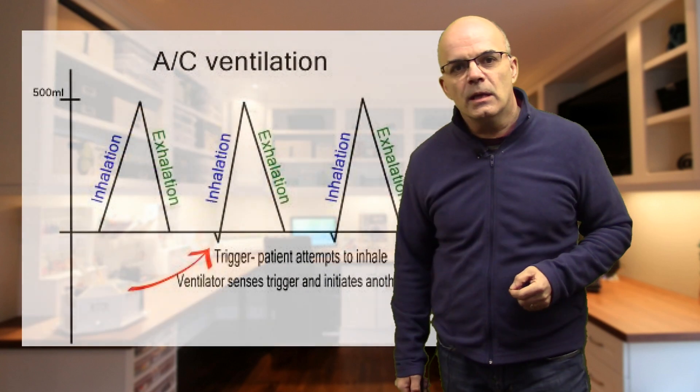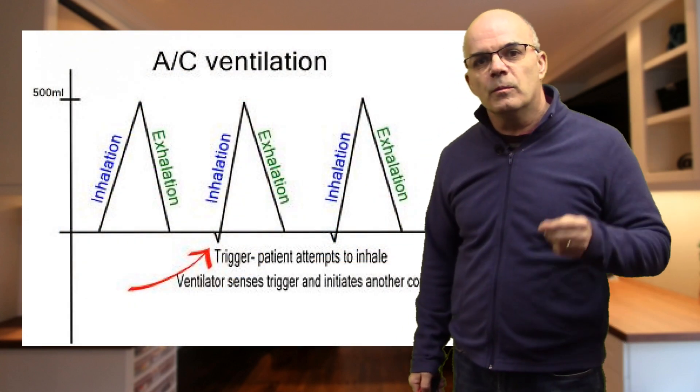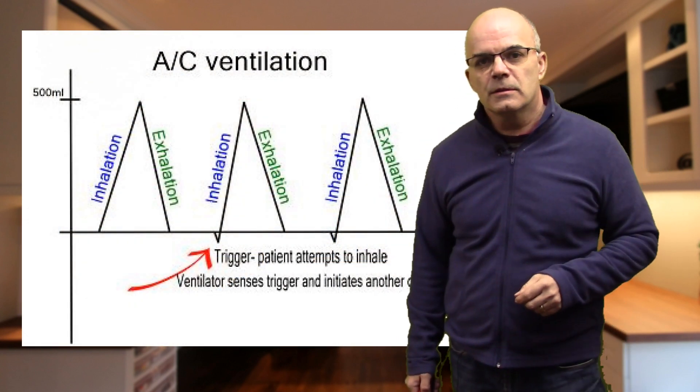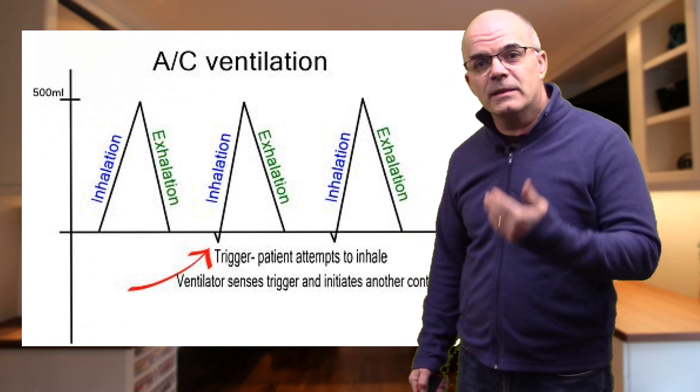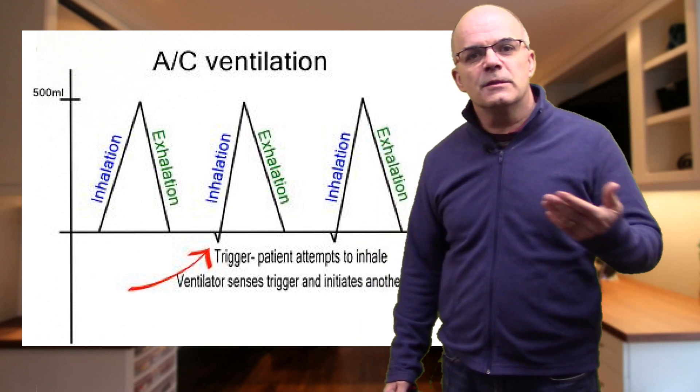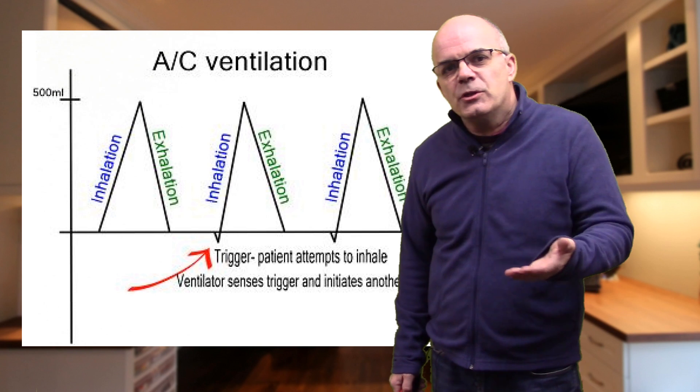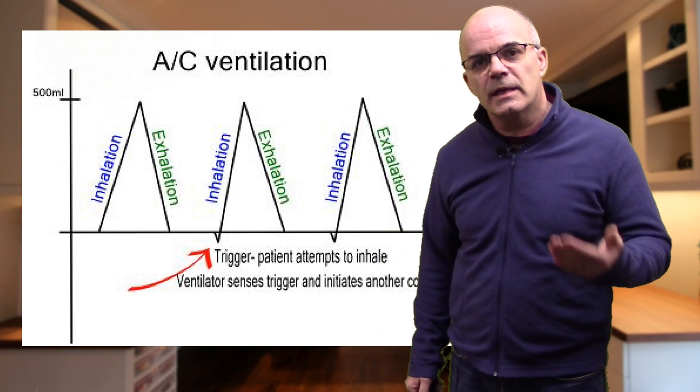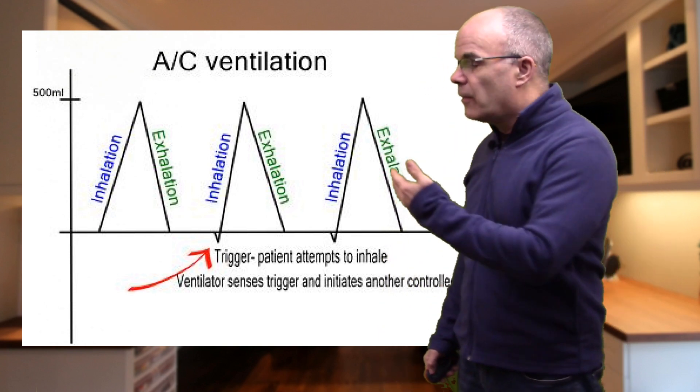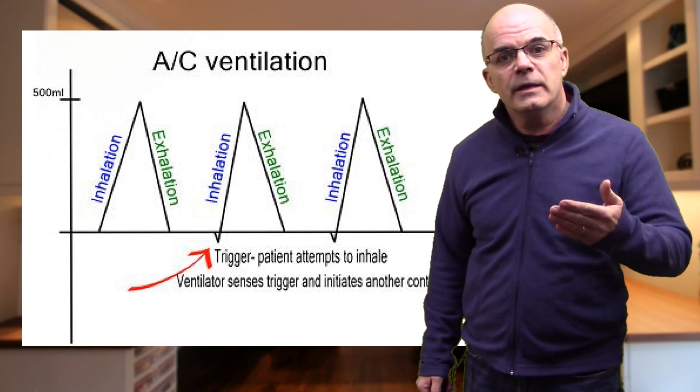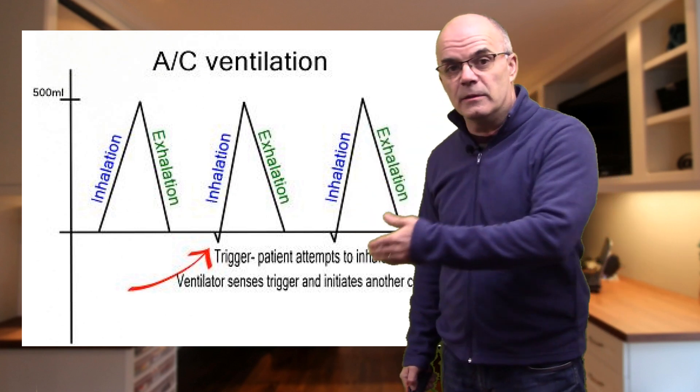If we look at the example here, we can see that the volume has been set to 500 mils. The first breath delivered is a mandatory one. Maybe the set rate is 15 breaths per minute and the patient has not initiated a breath within the set time, so the machine then delivers the set breath to the 500 mils set.